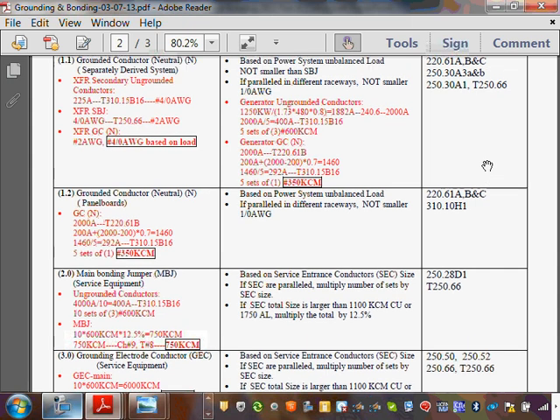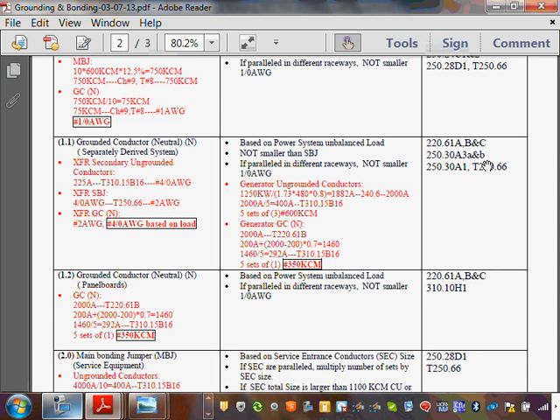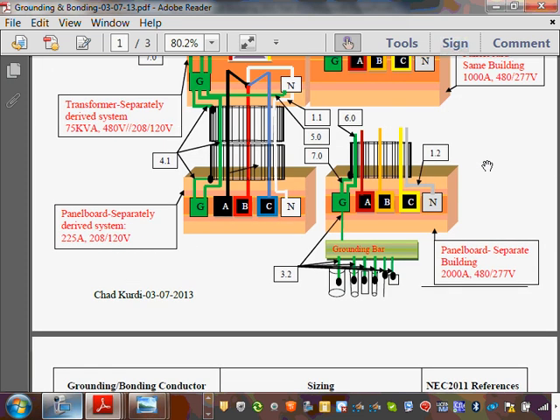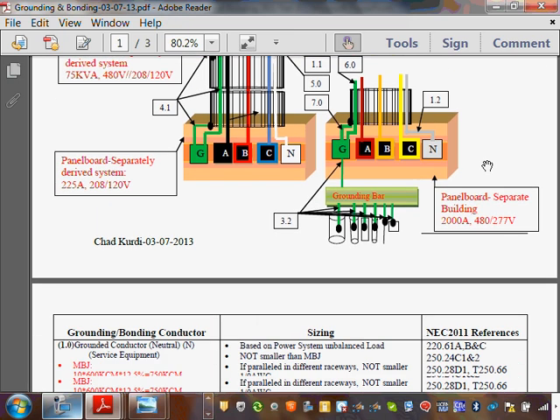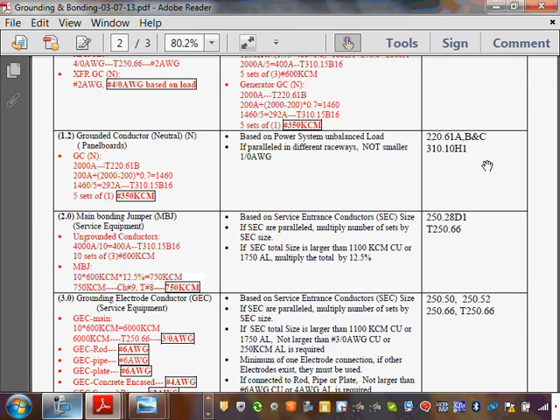1.1 right above it, the 100 amp. So we have, what was it, 1.2, 2000 amp. What was that number for? Okay, for the supply side bonding jumper. Can't remember. I don't know if 1.2 and 1.1. Oh, both of them are 1.2. Okay, that's why. So that's how I size it. I size it for one of them. 1.2 for the 2000 amp. For the 1000 amp, the same thing, guys, except you put 1000 amp here. So 1000 amp minus 200 multiplied by 0.7, and add in 200, gives you this number. How many runs do you want to run? You have to know how many runs because you paralleled it. I'm running 5. That gets you this amp. And that's how you size your neutral.